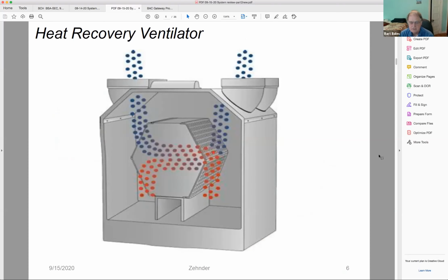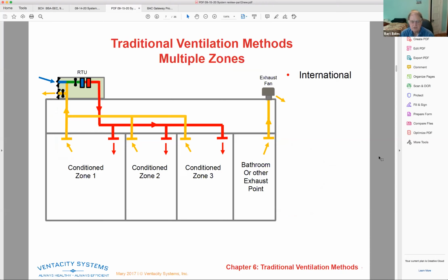Go ahead. This is just showing you how that system works. It's counterflow through the middle of that hexagonal shape, and that gets maximum heat recovery. Go ahead. So typically you have rooftop units or air handlers that are delivering air into the space, and then they're returning some air out of the space, maybe exhausting some air at the rooftop unit, and then there's also independent exhausts like fan exhaust that are letting air go out. You can see by this design, you have no heat recovery going on. You're losing the thermal energy in the air going out of the building, and therefore the air coming in needs more energy to be heated up to temperature.